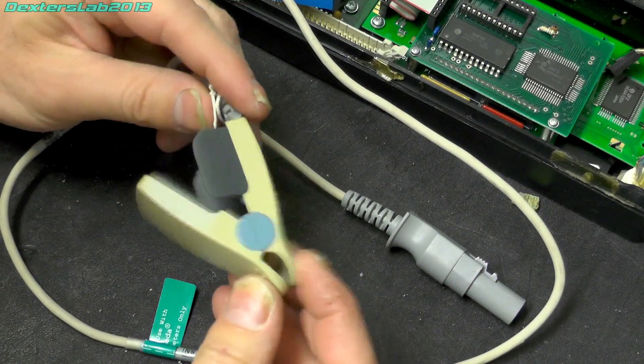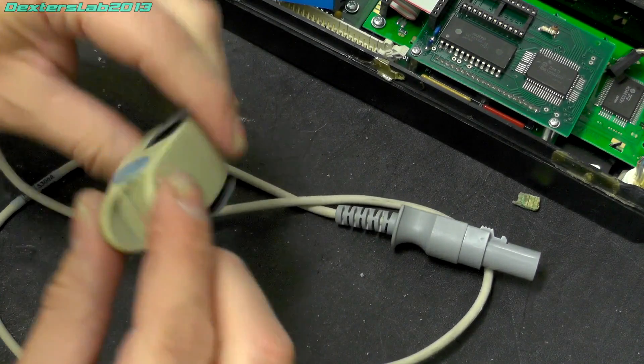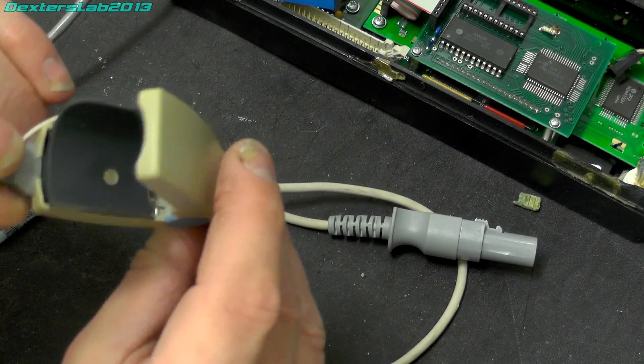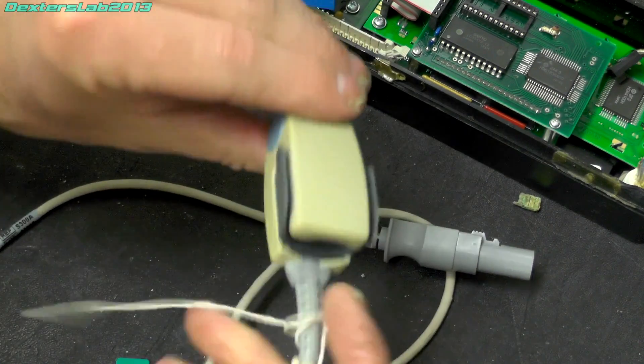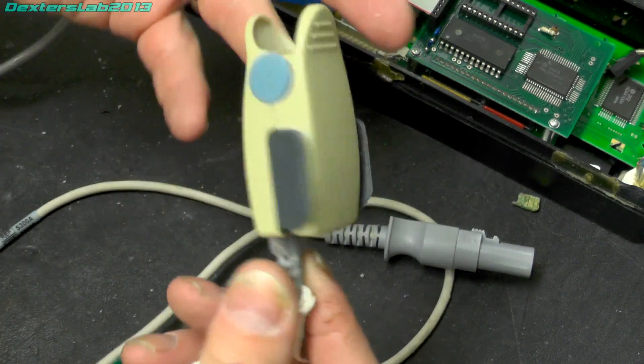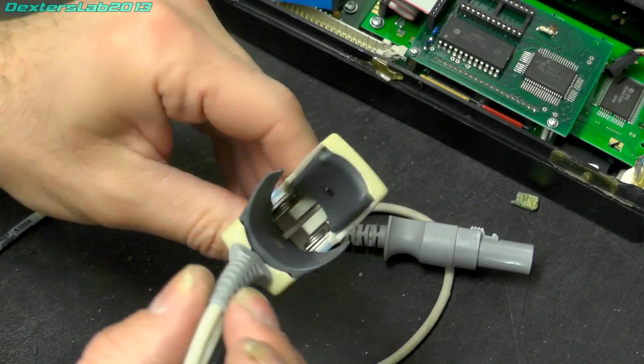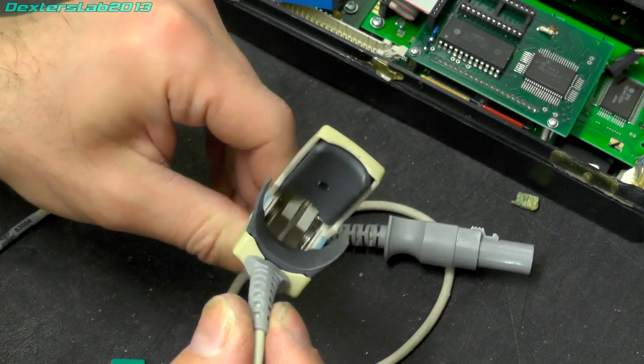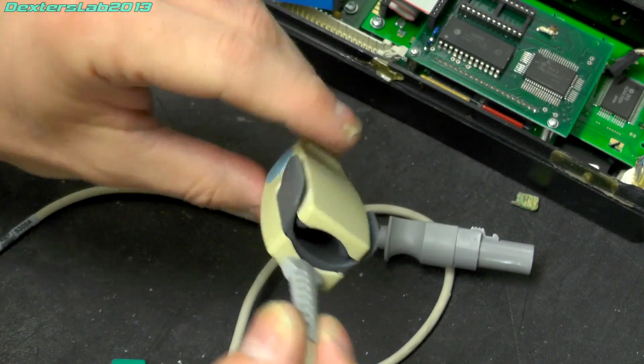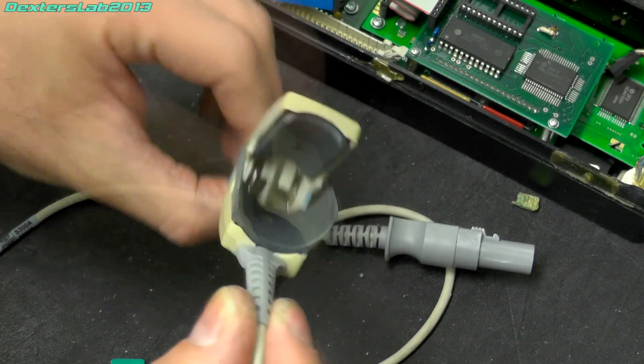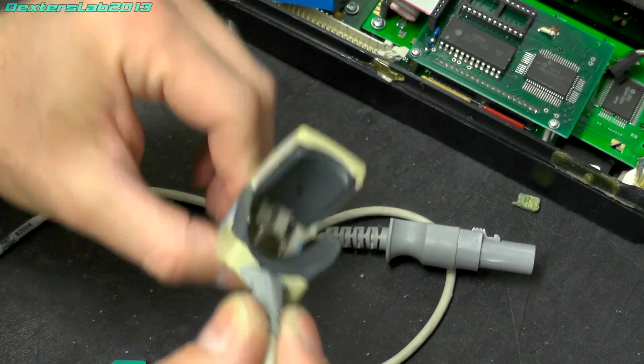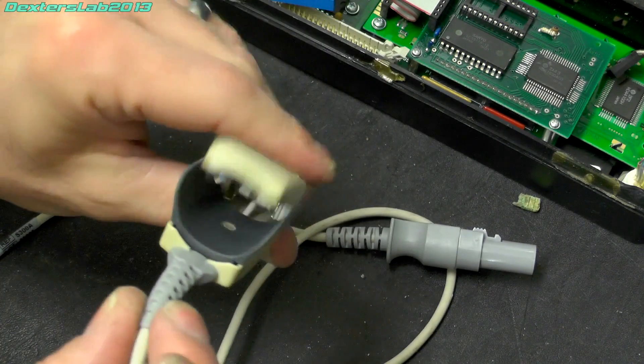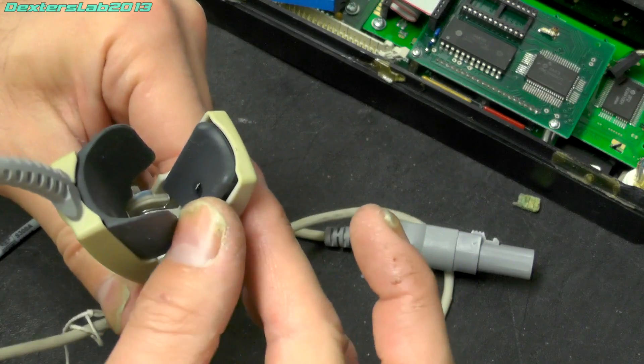So we'll have a quick look at this finger probe. So it's very simple molded bit of plastic with an infrared and a red LED in. And the way these work is they measure, depending on the level of the oxygen saturation in the blood, it will either pass or attenuate infrared light and red light and they work opposite. So when it's passing infrared light it's blocking red light and vice versa. Simple thing to measure it seems, so yeah, we just got two light sources and a sensor.